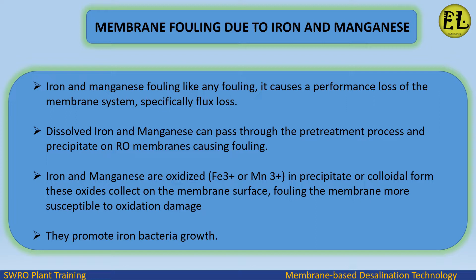Iron and manganese are oxidized to Fe3+ or Mn3+. In precipitate or colloidal form, these oxides collect on the membrane surface, fouling the membrane and making it more susceptible to oxidation damage, and promoting iron bacteria growth.